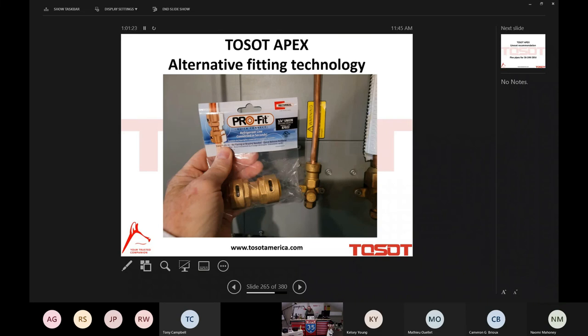And the value here is time savings, right? I mean, incredible time savings. I did my entire Apex installation here at the house, my entire flare. I take that back. I had to make two flares, and that was at the 3/4-inch connection at the indoor and outdoor unit. Why? Because Rector Seal has yet to come out with a 3/4 by thread connection. You can see that they have it for the 3/8, but they don't have it for the 3/4. So that was the only two flares I needed to make.